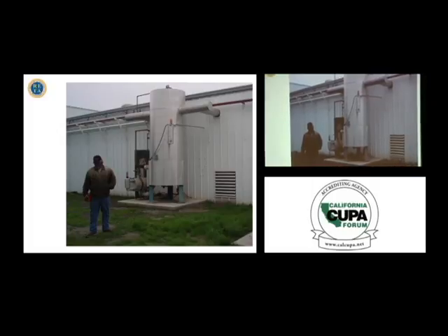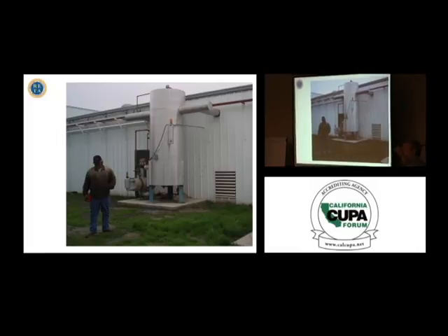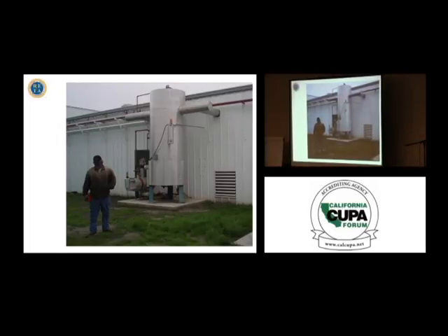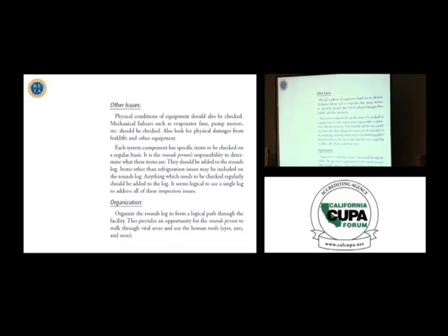If that is happening too often, that tells me, hey, we've got a problem somewhere out there. This is not supposed to be a recirculator. It's an occasional functioning thing. So that tells me as the plant engineer, it's time to go look to see what is causing an overfeed, such as you go to your PHA. What if the valve sticks open that is feeding the unit? What are the consequences? So that's how you use the benefit of the PHA to resolve a problem, or to even make a person aware of the problem.